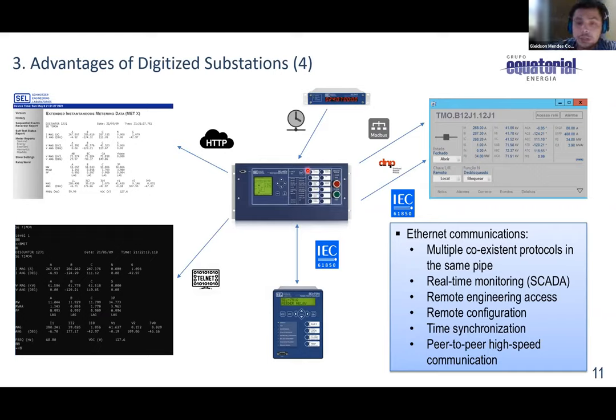We can have time sync protocol communication, so all the data of all equipment is synchronized. Modbus protocol, the DNP3 protocol. So the SCADA communicates with the relays through the DNP3 protocol. This is an interface that we have in Equatorial that we use for monitoring and controlling all the equipment, and it is done through DNP3 protocol communication. And P2P high speed communication, where relay to relay can communicate for high speed actuation.